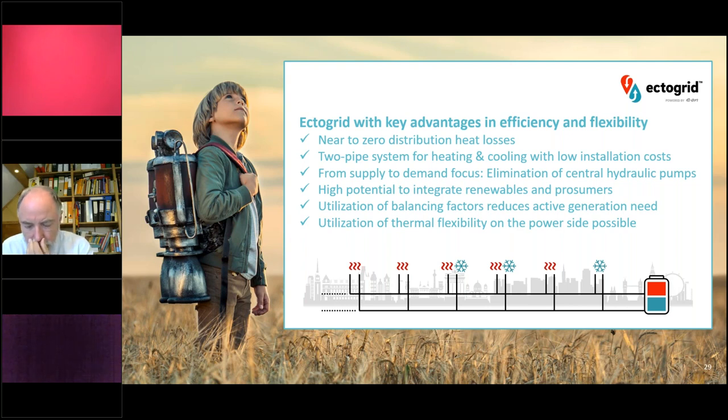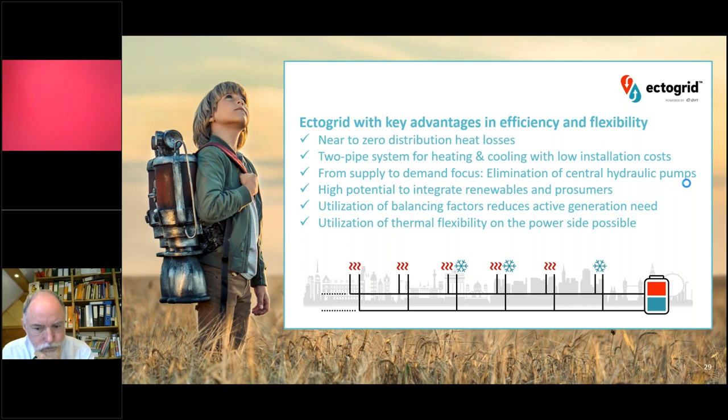Moreover, the system allows for balancing effects between heating and cooling needs, and that is really key. For instance, the excess heat produced by the generation of cooling, e.g. for a data center in the district, is being put into the network and can then in turn be used to optimize the COP of the heat pumps in buildings where at that point in time heating is needed. Finally, the flexible system temperatures themselves and also the storage capacity that I outlined allow local balancing towards the power grid, and this is key for our question here. Next slide, please.